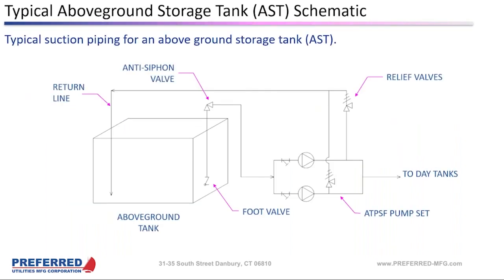So this is typical of an above ground fuel schematic. It's very similar to the underground fuel schematic, with the exception that we're going to have an anti-siphon valve between the main tanks and the pump set. And the anti-siphon valve is another thing that's out in the air that can freeze up.